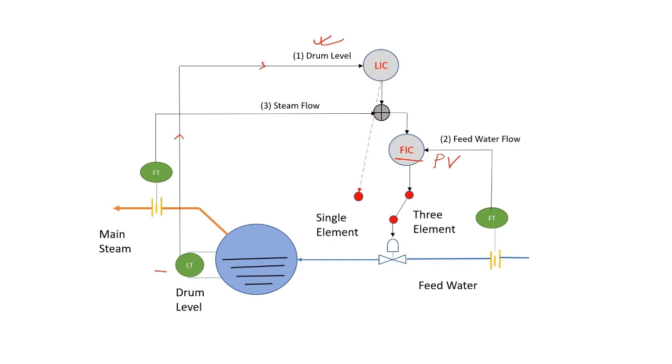Output of this level controller becomes the set point of the flow controller. This becomes the master and this flow controller becomes slave, so this is a master-slave cascade control scheme.